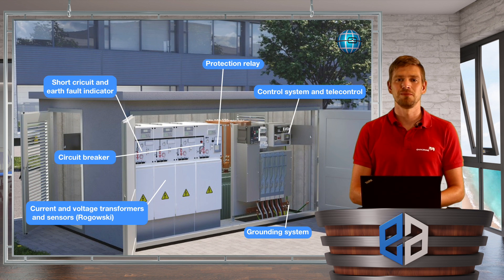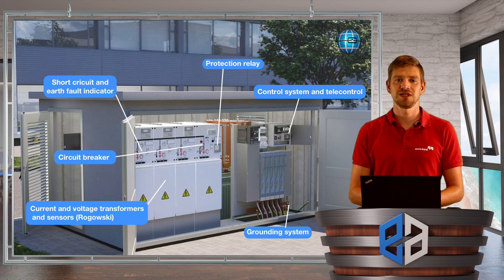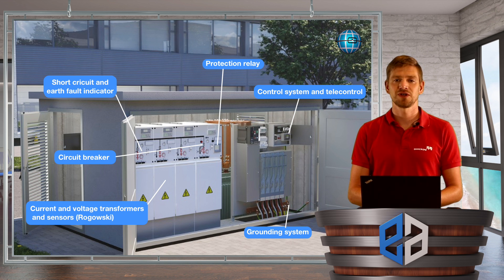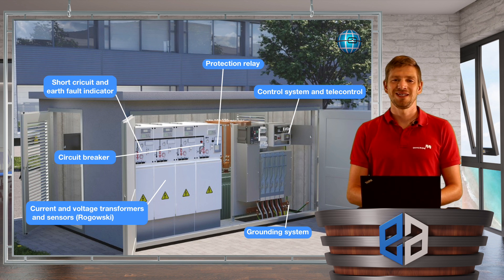Here is an overview of the modern components. A ring main unit consists of more than these components mentioned here, but we see these components coming in due to new requirements in the electrical power grid. On one hand we have the short circuit indicator and earth fault indicator, which are becoming more common as more cables go underground and we need to detect faults in the power system. These short circuit and fault indicators also give you values of current, voltages, and even the power flowing through the secondary distribution grid, and they can even switch some load breakers.